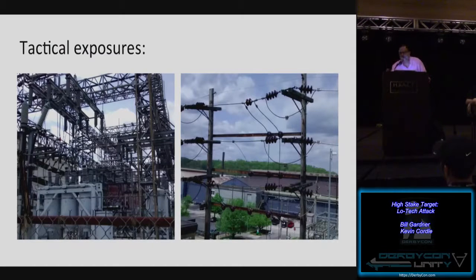They can also be set to go off instantaneously, but very few are. The idea behind reclosers out on the line, and station breakers in the station, is that if a tree falls on the line, let's burn it off—drop it to the ground and go check it later. That's why if your power blinks once, twice, three times, you're probably going to lose it.